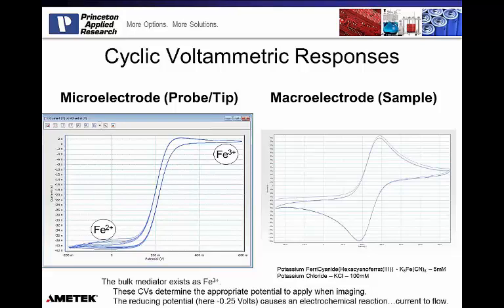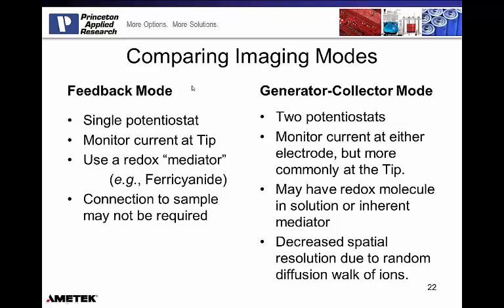So now I've taken my 3-electrode electrochemistry, I've done it on my probe. Now I'm going to move over and do 3-electrode electrochemistry on my sample. Really what I'm looking for here is that my sample is polished and clean and gives me a typical response that I expect. And you can see your duck-shaped CV gives me the response that I expect from a 5mm gold disc in a ferricyanide-ferrocyanide couple. That kind of diffusion-controlled Nernstian type response.